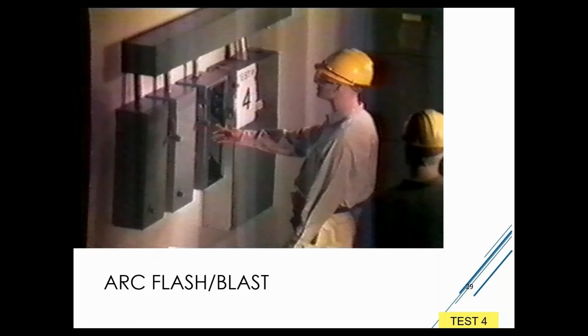So from this event, one of the things I want to mention right now, because I know we're not going to have a lot of time to talk about it today, is the term working distance when it relates to arc flash. Most arc flash labeling or arc flash energy information will give you a working distance, let's say, of 18 inches, and it really relates to the type of equipment and how deep the equipment is. Is it standard equipment like this one where they use an 18-inch working distance, or is it something that's deeper, like larger equipment that's 24 or 36 inches deep? It's really the distance between the source and the worker's face or chest area.